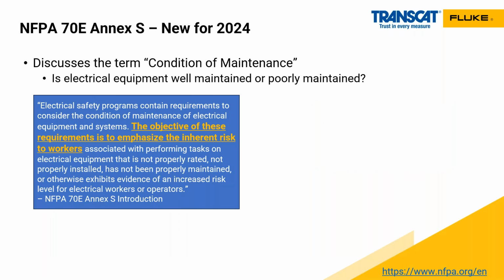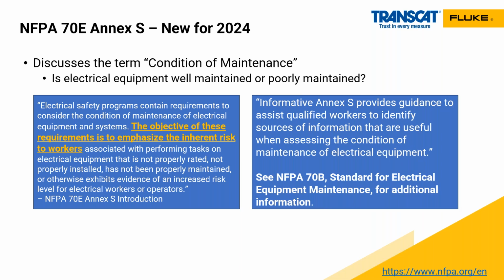So to back up a step, 70E, the Annex S, really gets into the condition of maintenance. That's an electrical safety standard, but is the equipment well maintained or poorly maintained? The object of all this is that properly maintained equipment will be safer, or should be safer. This is also giving the worker who's working on these types of equipment and circuits the ability to assess the condition in terms of the maintenance, or the electrical health, of those circuits.